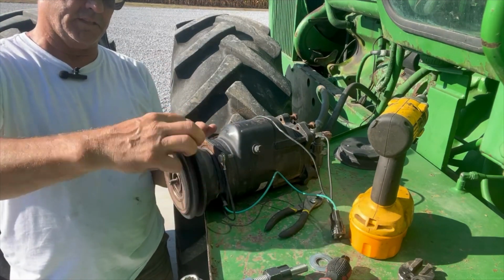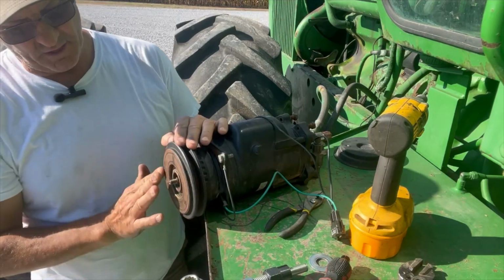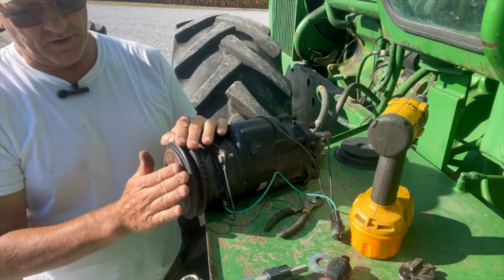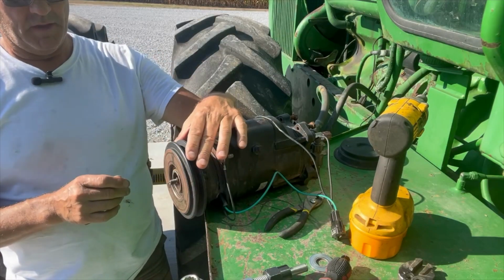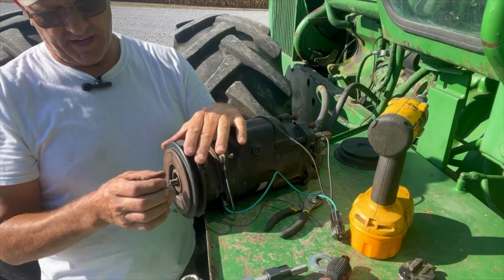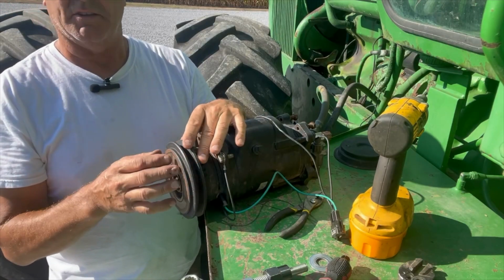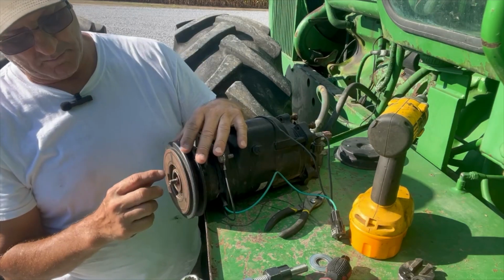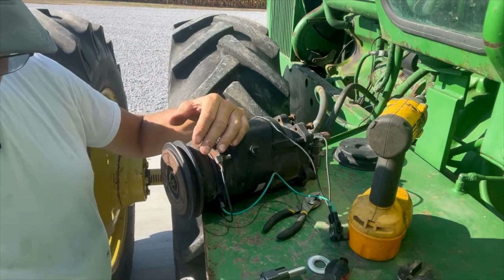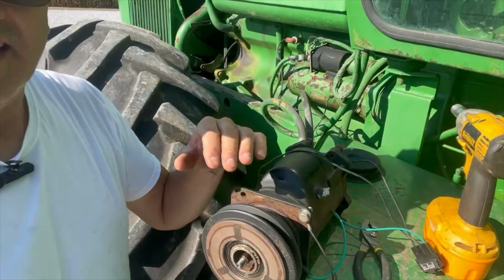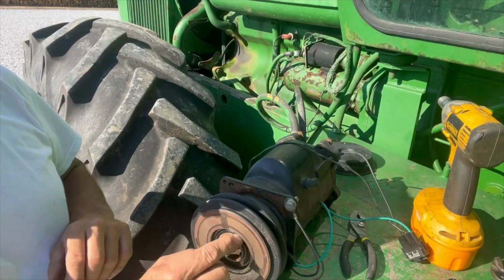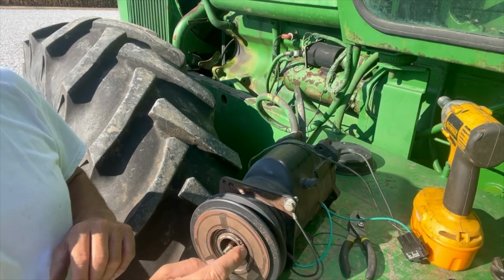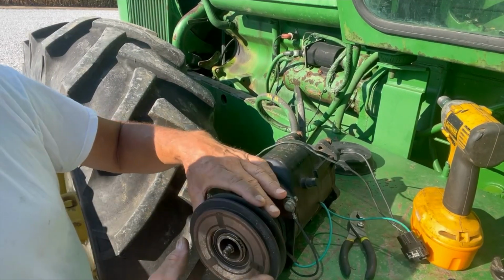If the pulley groove is good and the face of it can be cleaned up to be very true, then you can replace the bearing in it and put the whole pulley back on the compressor. But I'll pull the camera around here a little bit - as you can see, there's a snap ring in there that holds that on.